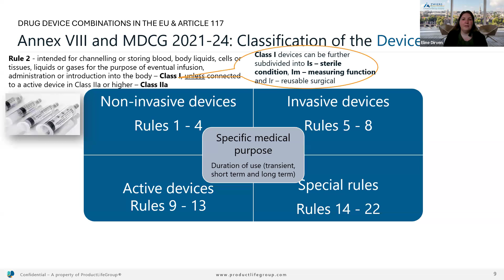So if we go to the non-invasive devices, we see that pre-filled syringes, which don't have any needle attached to them, could fall under Rule 2. Those are intended for channeling or storing the medicinal product for the purpose of eventual infusion, administration, or introduction into the body. And those can be classified as class 1 devices, unless they are connected to an active device, which might, for instance, be a transfusion pump. Then it might result in a class 2A device. It's also good to realize that in case it is just a class 1 device, because you connect it to a needle or maybe to a more gravity-based transfusion set, for instance, then you need to further subdivide it. So you still need to determine whether there is a measuring function and/or whether it's in sterile condition. So that's also, if Tom presses one more time, visible on the slide.